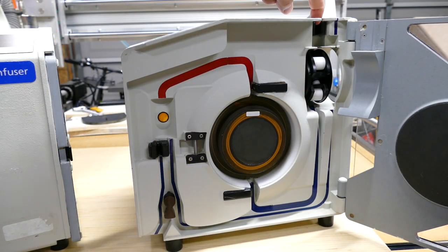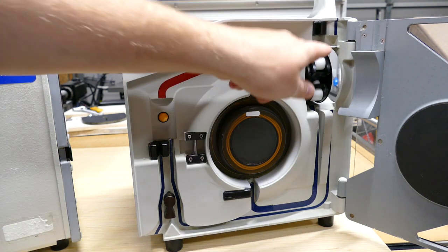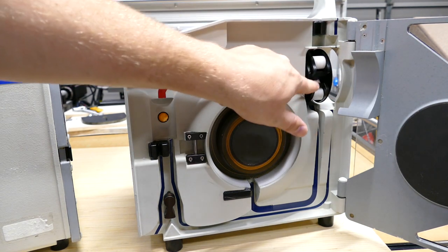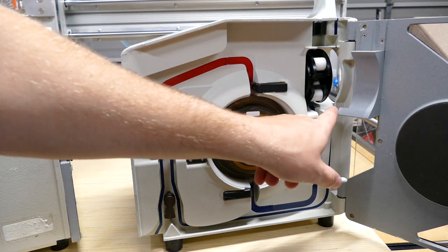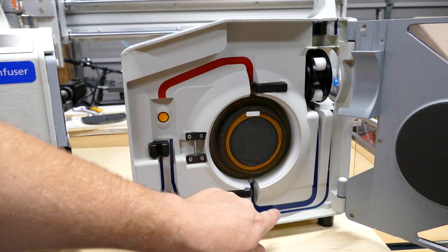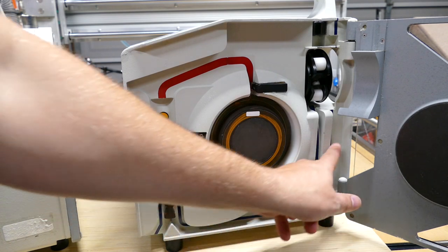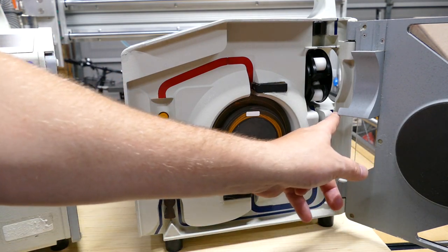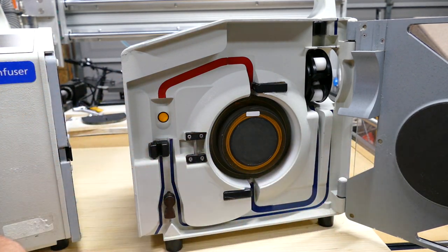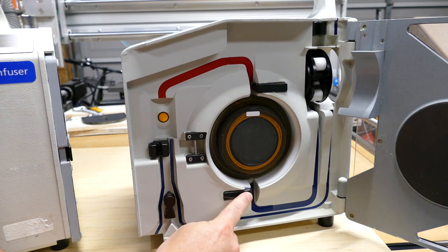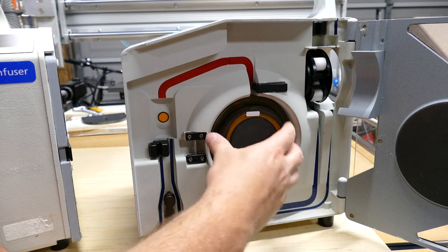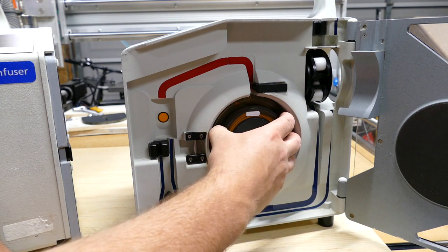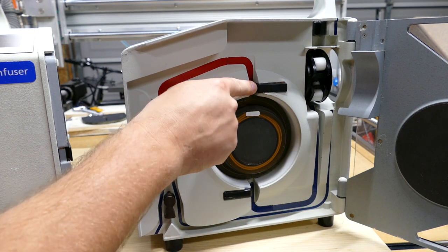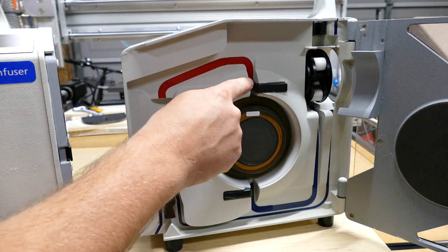Here is where part of your cassette will get loaded, and this is your fluid out detector. It goes across this peristaltic pump. You'll have two lines that run down. One of them is your main line. The other one is your recirculation line or your priming line. It comes up right here through your input infrared sensor, goes around the induction heating coil, and then it exits out here where it turns into the red line.